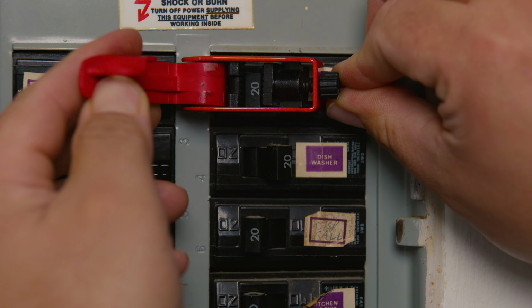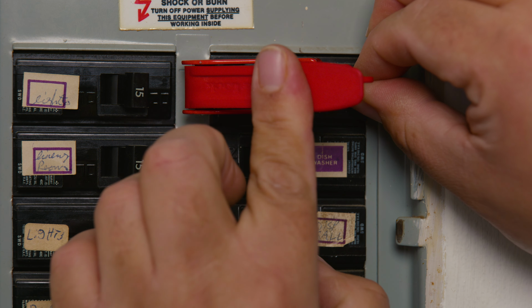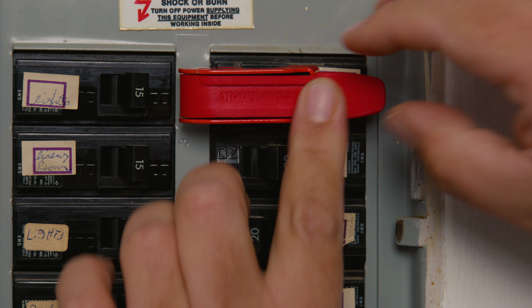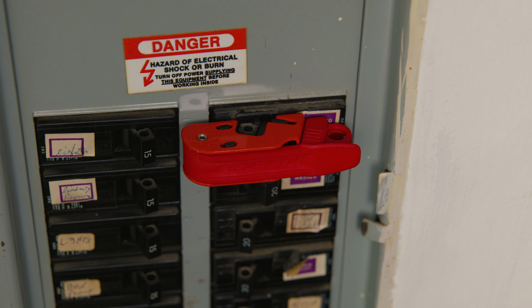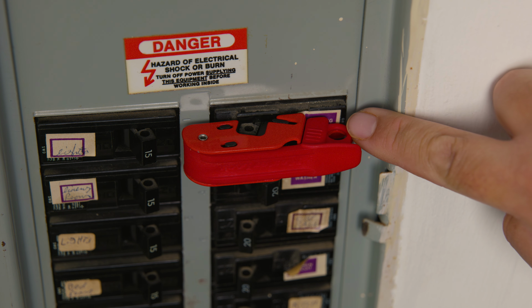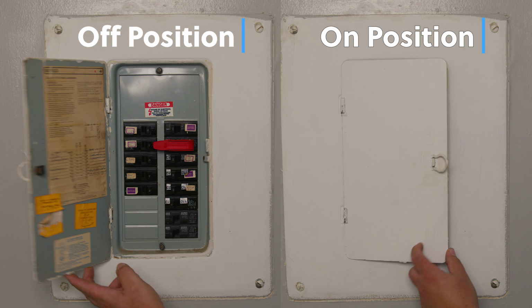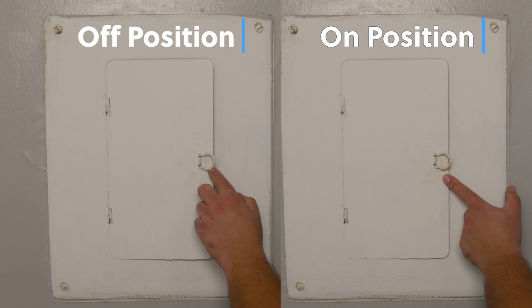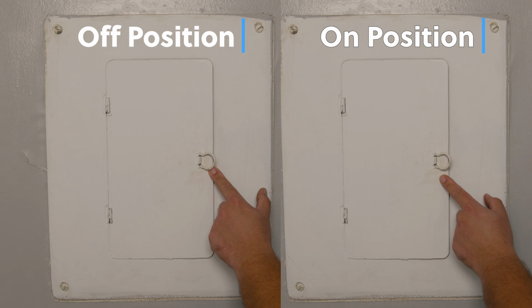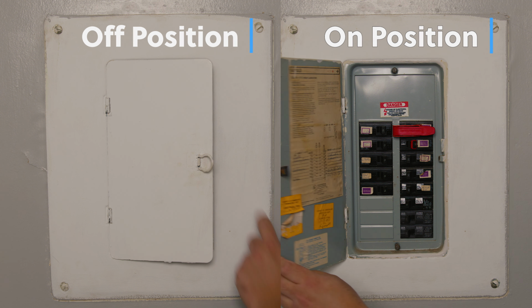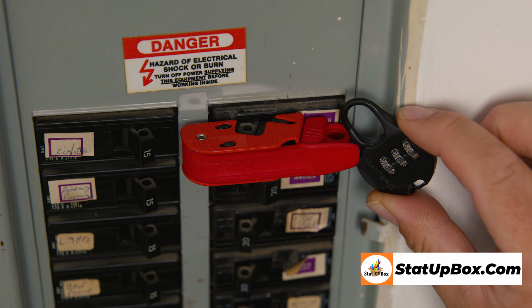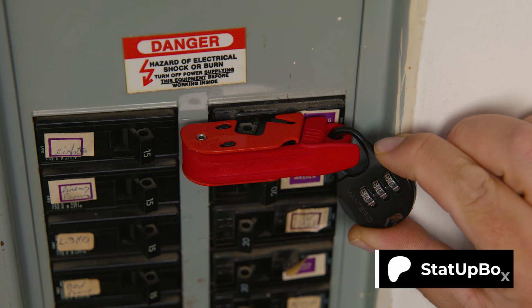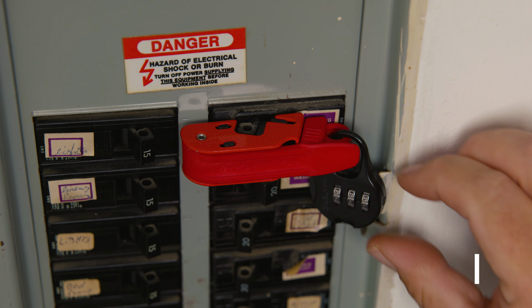And no matter if you're placing the lockout on a breaker on an on position or on an off position, what you want to make sure that you do after you install it is snug it a little bit, some side to side action, and no, not your body, and verify that it is tightly in there, because you don't want to place the lock and then it just falls off. What we have noticed is that depending on your circuit breaker panel, while having the lockout, some panels would not close. So that is something to take in consideration when installing. And now you've done it. There's no breaker that can escape your grip. You can pat yourself on the back for a job well done.